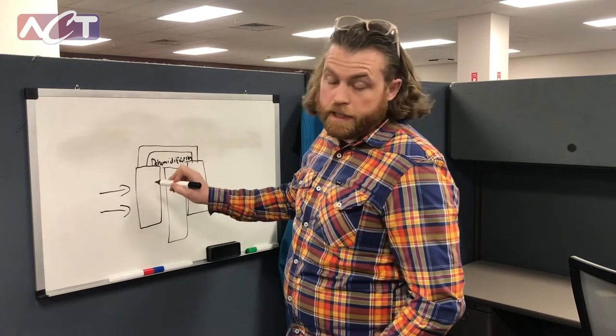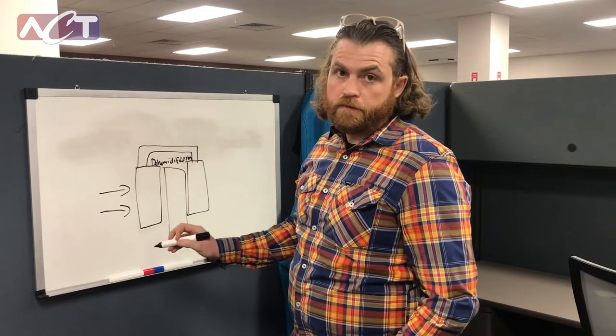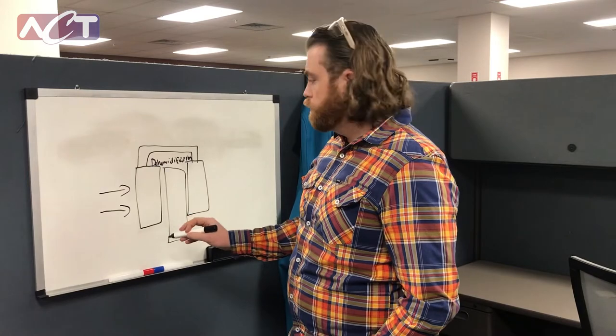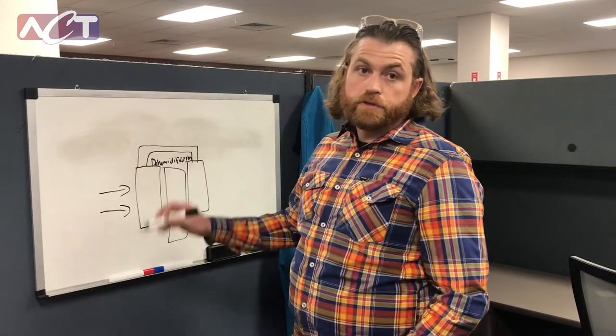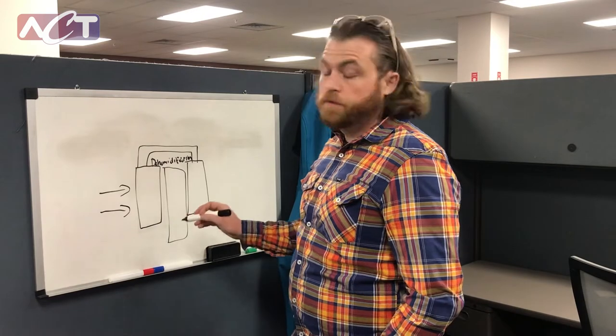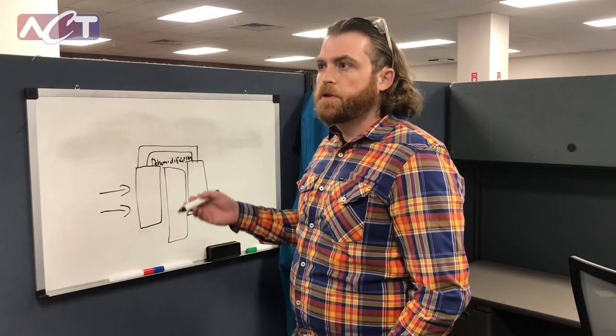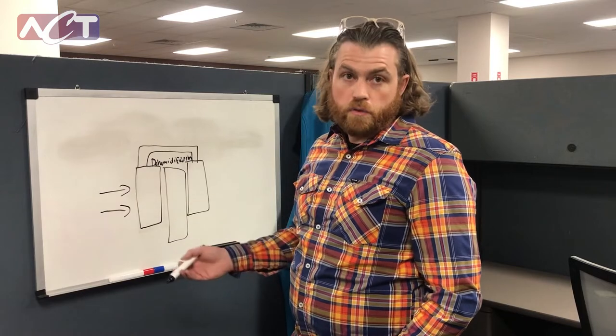performed at this front coil by reducing the temperature of the air and condensing out moisture before it gets to our cooling coil. Our cooling coil then reduces the temperature further and additionally reduces the overall moisture content of the air to the moisture content that's required for the building.